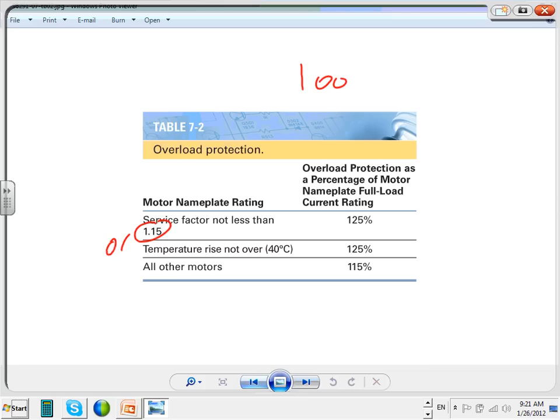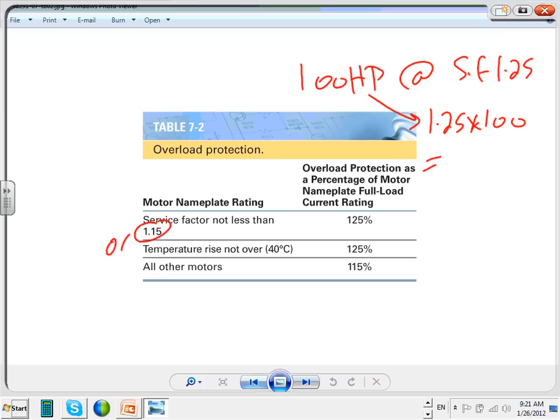If I have a 100 horsepower motor, and at service factor 1.25, or 1.15, I just picked a service factor, you can get to 125. This means this motor can be overloaded up to 1.25 times 100. That will give me 125 horsepower. Right, but what does that mean? What does the word service factor mean for this? The logic behind it is you can abuse the motor more. You overload it more. It can handle more overload, not forever though. I can't pull 125 horsepower forever.